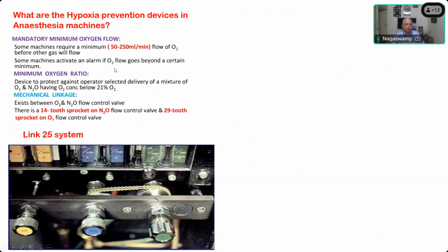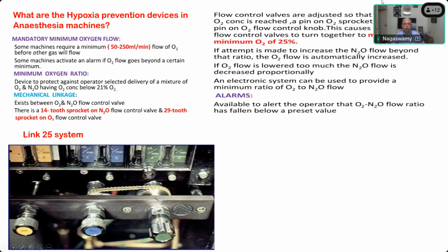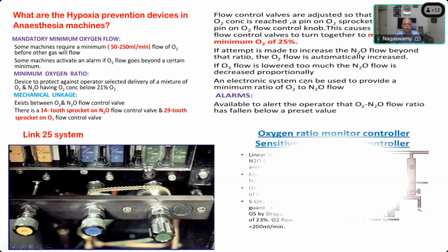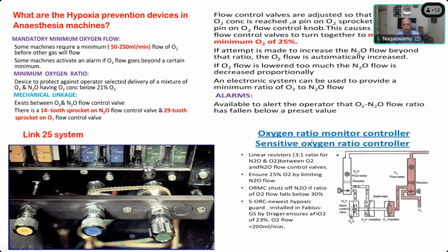Machines activate an alarm if oxygen flow goes below a certain minimum. There is also a minimum oxygen ratio used to protect against operator selection of a hypoxic mixture, and a mechanical linkage, that is the Link 25 system. These are all the hypoxia prevention devices. Flow control valves are adjusted so that a minimum of 25% oxygen concentration is always given to the patient, and alarms are there. The oxygen ratio monitor is again a repetition, so I will skip that.